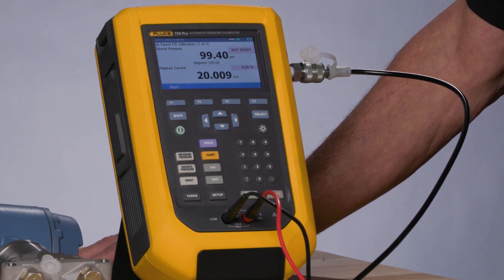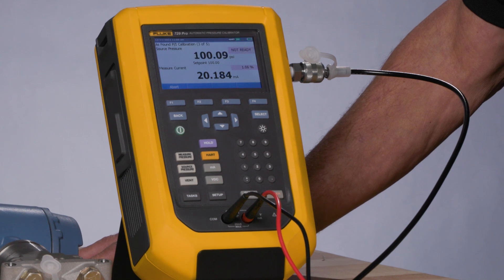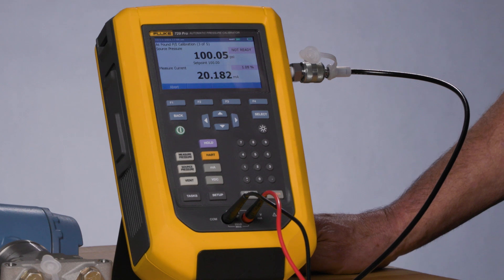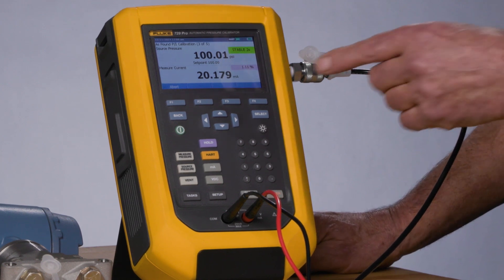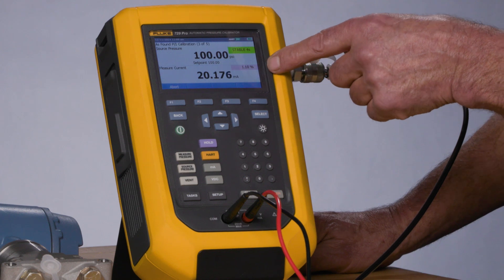Now it's going to 100 psi. And you see the milliamp value being recorded, and its error percent.